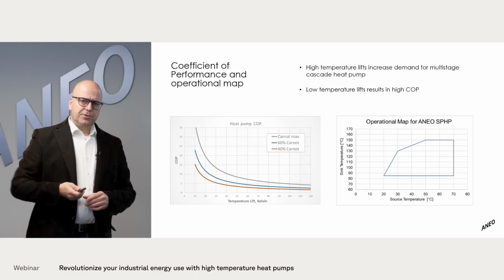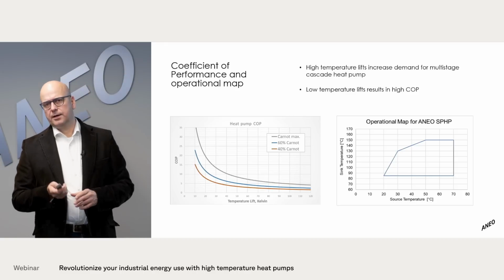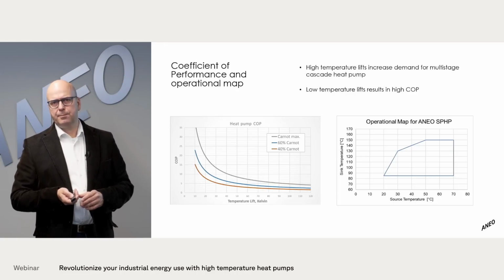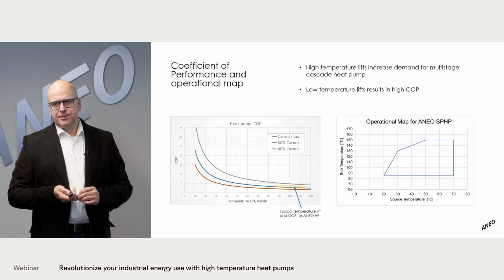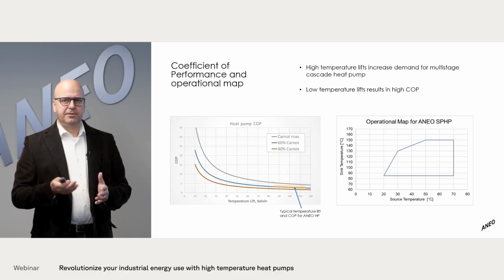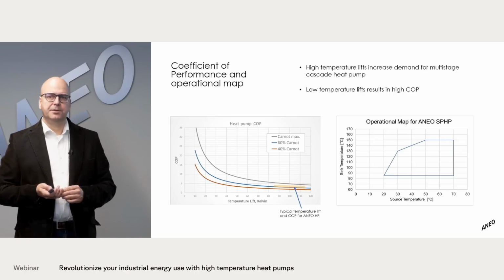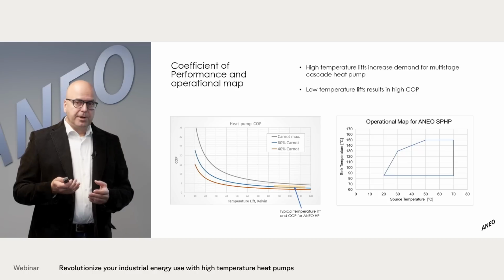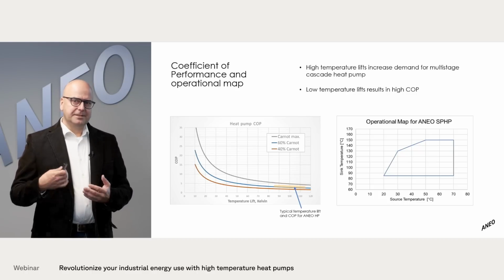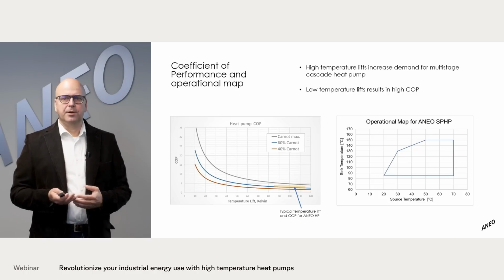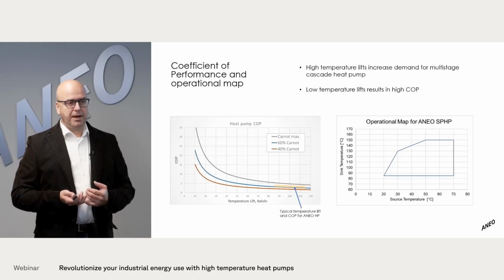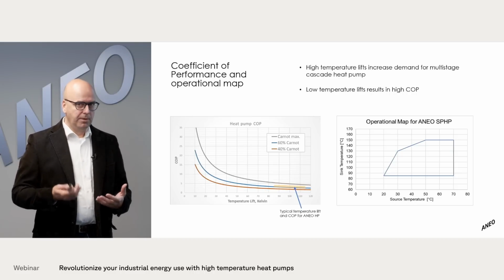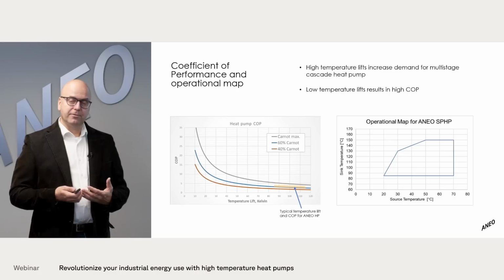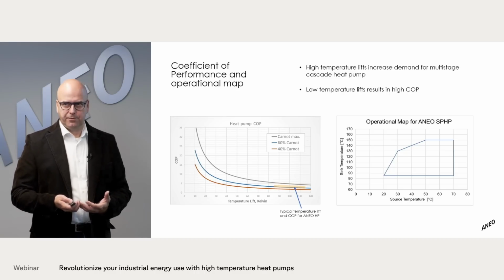If I put the technology setup together and bring it into this operational map for our heat pump system, we can safely say our heat pump is typically designed to deliver a temperature lift from 80-90 degrees up to 110-120 degrees, achieving a Carnot efficiency of around 60%. In this example, temperature lift of 100 Kelvin gives us a COP of 3.0, which is very important for the business case to give a good energy price to the customer.